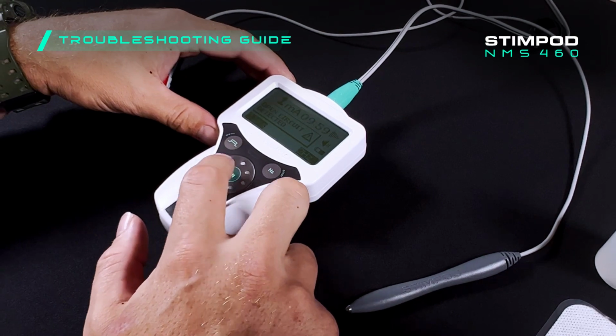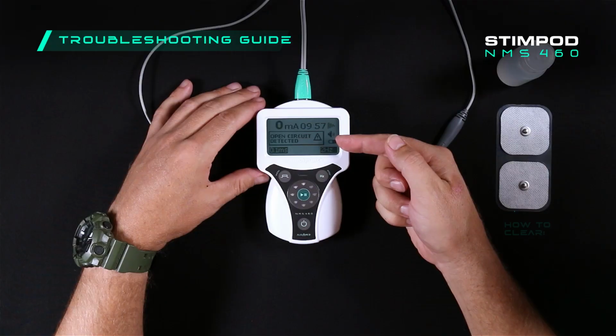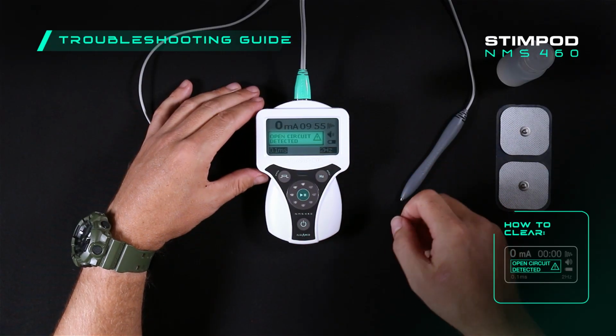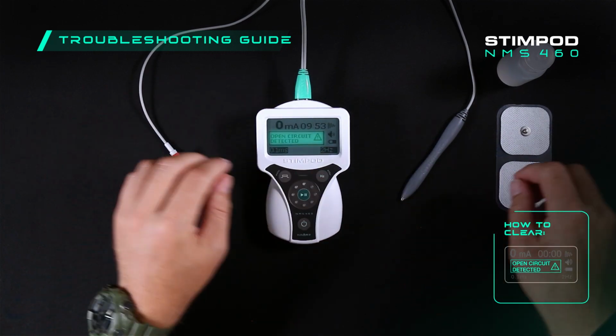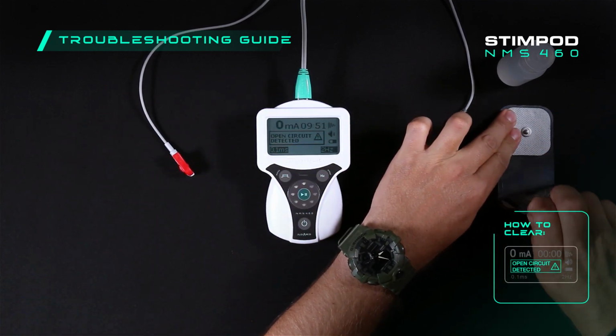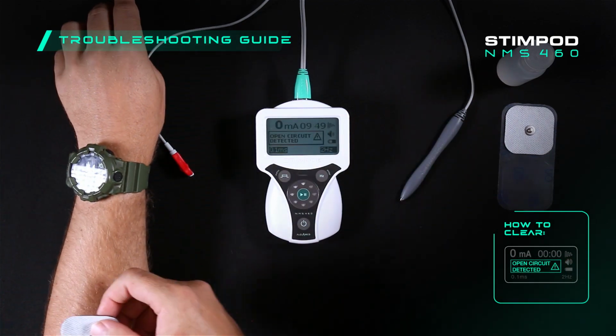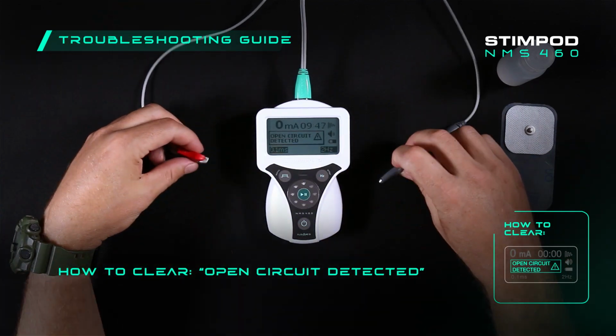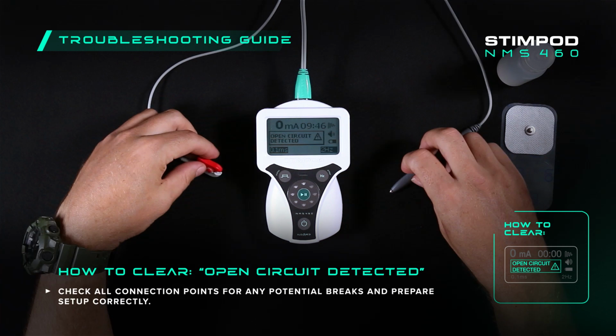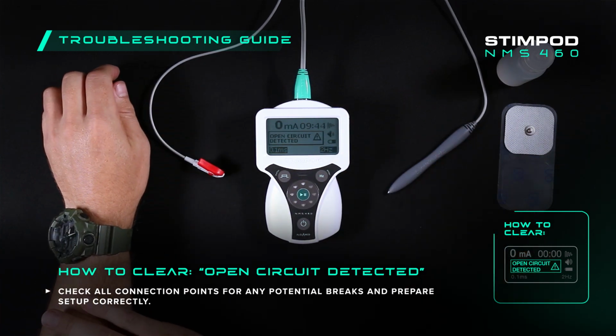One of the most common scenarios encountered when operating the Stimpod is the open circuit detected warning message displayed on the screen when treating a patient. This warning message simply means that somewhere between the Stimpod and the patient, the connection has been broken and needs to be addressed with the following basic steps.